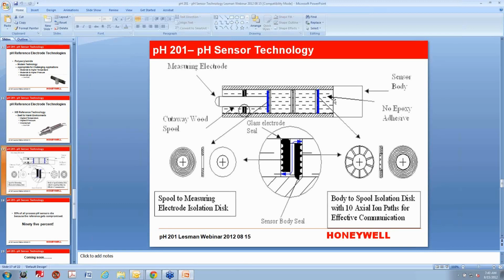And the reference electrode, and I forgot to put it in this drawing, my apologies, but right here at the back would be the reference electrode. It's 50 times the size of a standard silver chloride reference electrode. It's all the way at the back, and it's well protected. So if you were to take this sensor and put it next to any of those other technologies in a plain water application, it will probably have the same lifespan, because the lifespan in that application is going to be based on the active sites on the glass, how soon they wear out and get coated up. But the nastier the process gets, the better this technology looks.